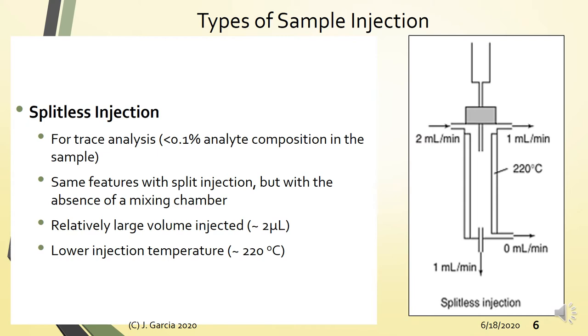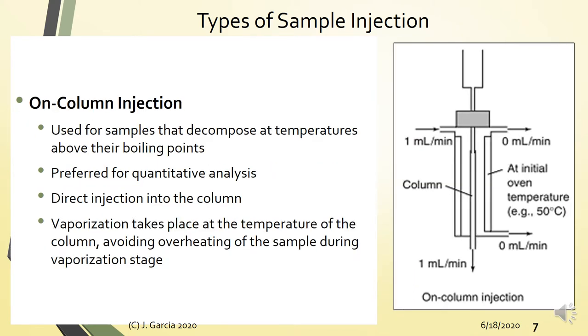To summarize: split injection is for more concentrated samples, while splitless injection is for trace analysis with lower analyte concentrations. The third type is on-column injection, used for thermally labile samples that decompose at temperatures above their boiling points. Here, the sample is injected directly into the column where the temperature equals the column oven temperature, so vaporization occurs at the column temperature, avoiding overheating during vaporization.